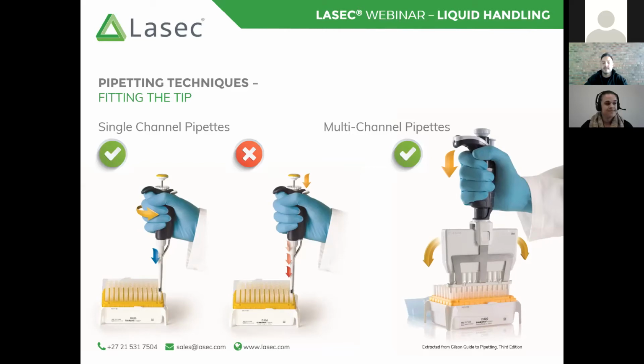We do see it with the small volume pipettes that sometimes those tip holders, after being banged into the tips, do slip and those holders now point at a 90-degree angle almost. So really try to avoid banging your tips into your tip racks. If you're finding that that is the only way to fit it, use different tips or more appropriate tips.